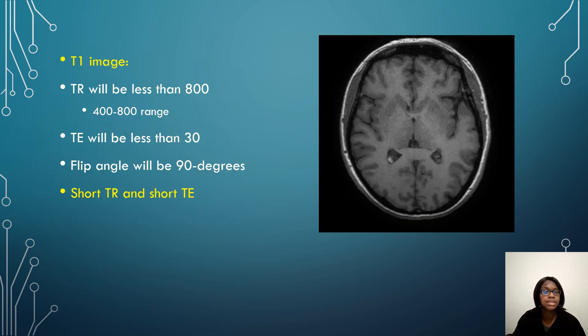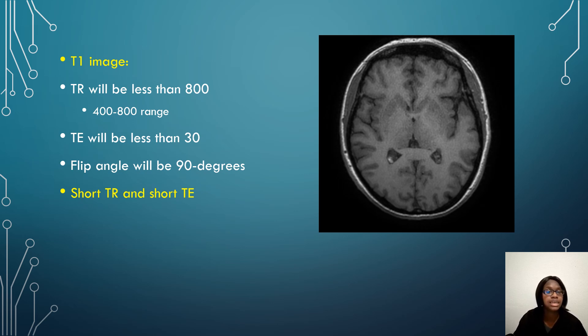For your T1 brain image, the TR will be less than 800 — a good range is anywhere between 400 and 800. The TE will be less than 30. The flip angle will be 90 degrees. It will have a short TR and a short TE.